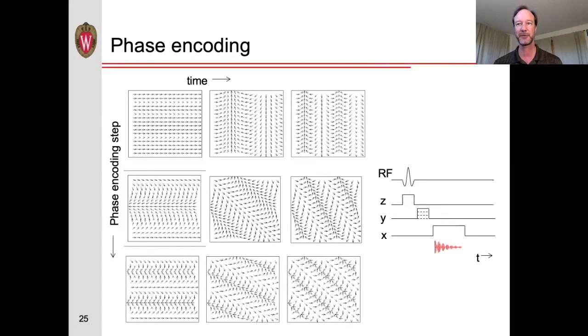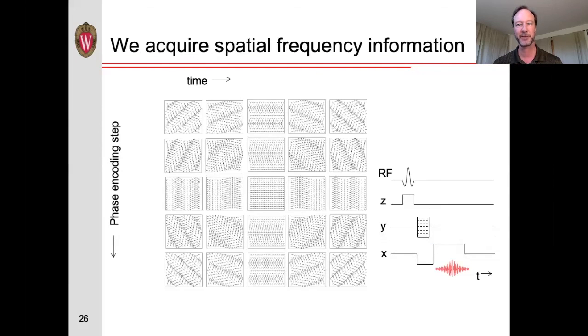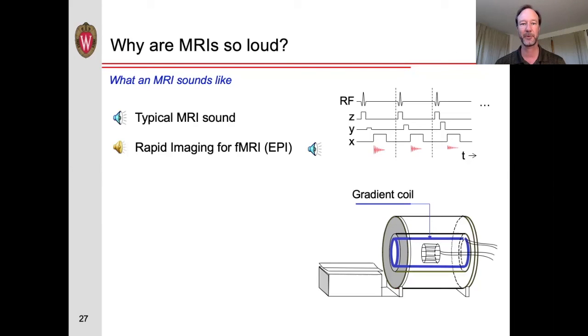Note that how the magnetization vectors are twisted up in the first column is very similar to what is going on in the first row, except that the twisting is in the y instead of the x direction. In this way, just as we can find out where the signal is coming from in the x direction by looking at the frequencies present in the signal acquired in these rows, we can find out where the signal is coming from by looking at the frequencies present in the columns. The only difference is that the frames that you see along the x axis were acquired closer together in time, snapshots of time while we are acquiring the data, rather than across different phase encoding steps, shown in the y. What I was showing you was actually just part of the picture. We're actually acquiring the phase twisting in both directions. The middle line is without any phase encoding, and the top is twisting in one way, the bottom will be twisting in another way.